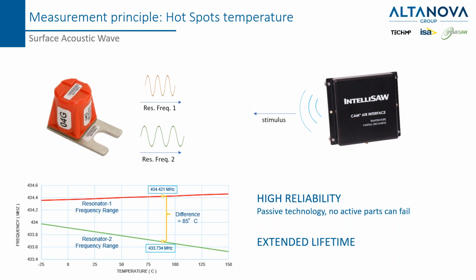This means that with a higher temperature, the material inside the sensor is dilating, and it also faces some restriction when the temperature goes lower. So it's the typical behavior of the crystal inside according to the temperature variation. And this difference actually represents the temperature measurement. One of the advantages of having this passive and wireless sensor is that passive actually means higher reliability and also extended lifetime.